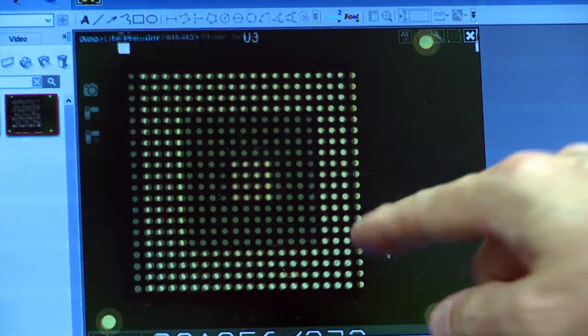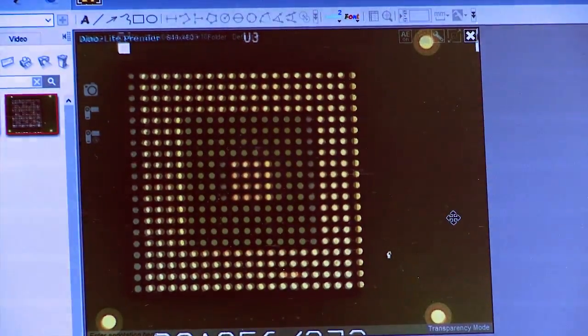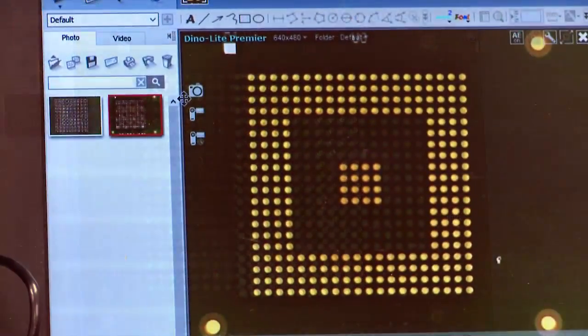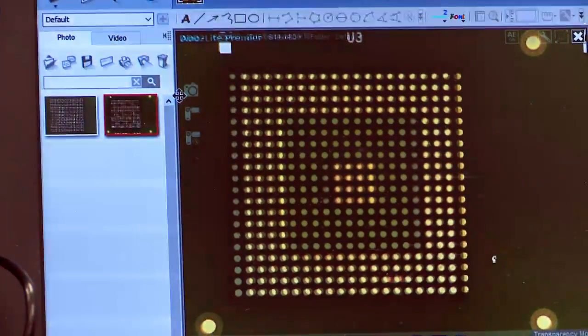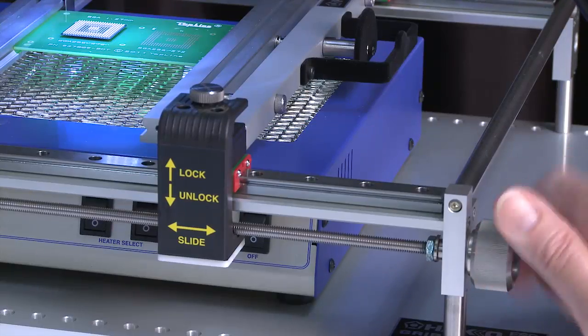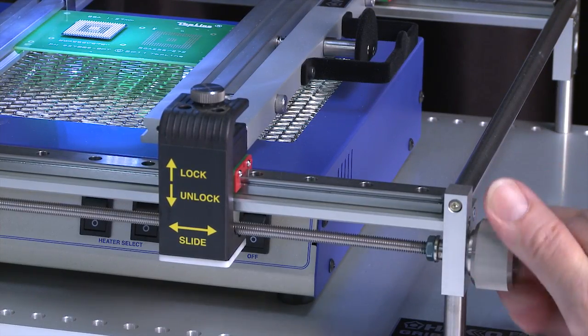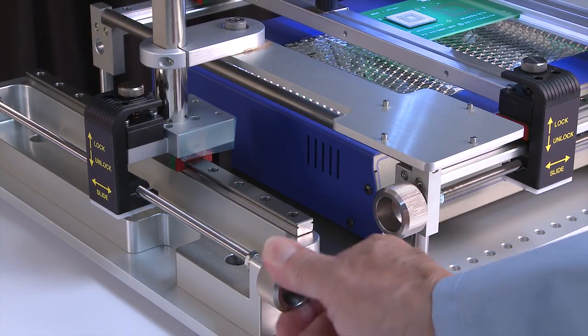Contrast and intensity can be adjusted as needed as well as the superimposed view of the component balls and grid array. Use the fine X and Y adjustment knobs to align the component balls to the grid array on the board.